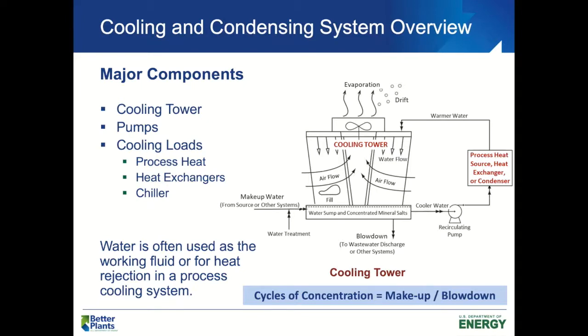Another thing that happens as it gets cooled down is the minerals that are there get solidified and drop down to the cooling tower sump, where it needs to be blown down so that it doesn't build up. So two things to note here are the blowdown and the evaporation, right? Because the blowdown, in addition to the minerals, also removes water, and of course we have evaporation that loses water as well. So the makeup water that we're going to be adding into the system is going to be the sum total of the water lost through blowdown and evaporation.